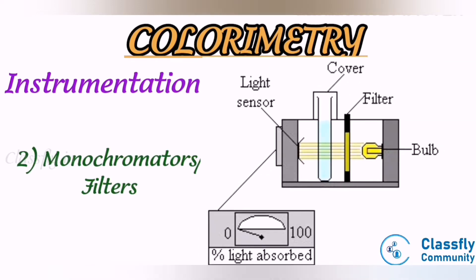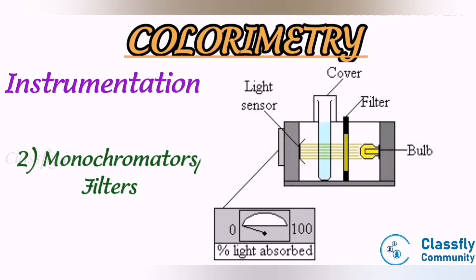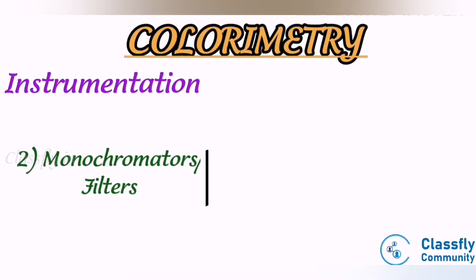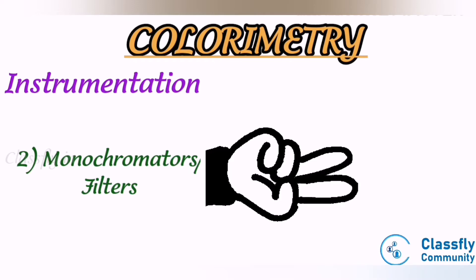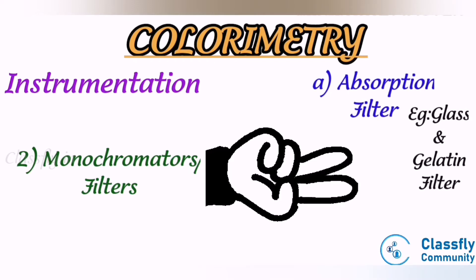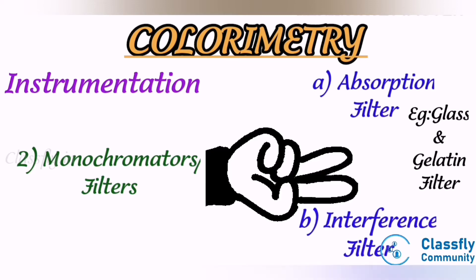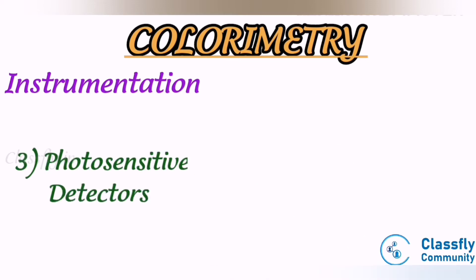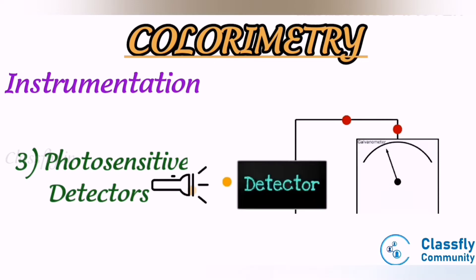Second, monochromators or filters: this is a means of selecting a sufficiently narrow waveband. Filters absorb the light of unwanted wavelengths and allow only monochromatic light to pass through. Filters are mainly divided into two types: absorption filters (for example, glass filter and gelatin filter) and interference filters.